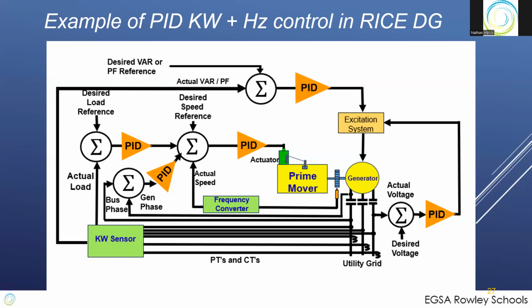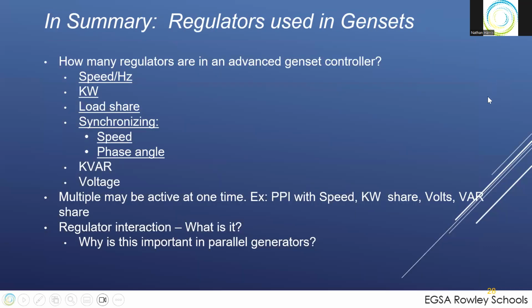This KW, kVAR sensor also feeds back VARs, since here's your VAR regulator and the PID in the excitation system. So this is all going on at the same time. It has to be tuned properly. That kind of summarizes, again, the regulators in a system here.